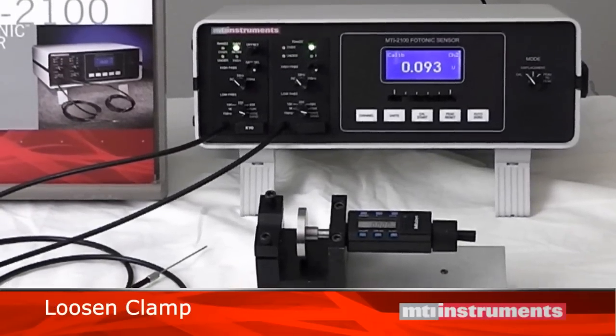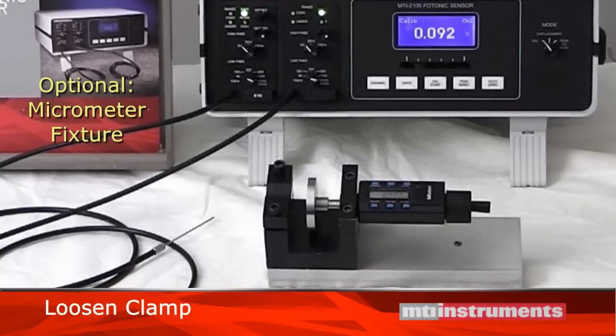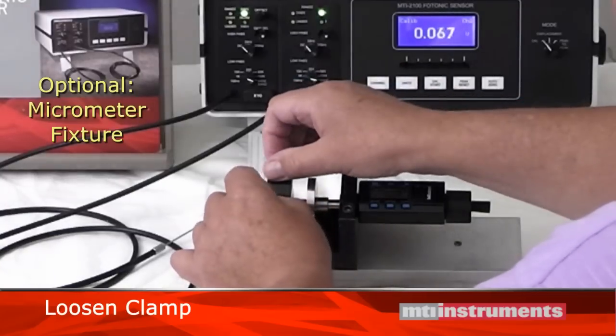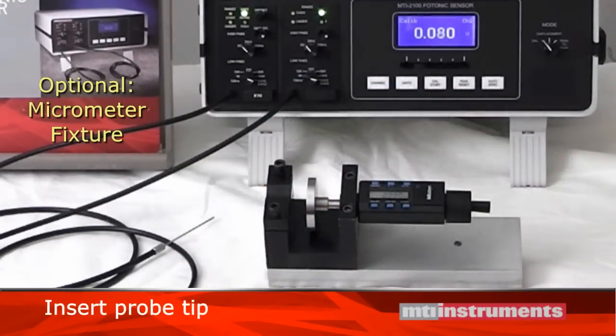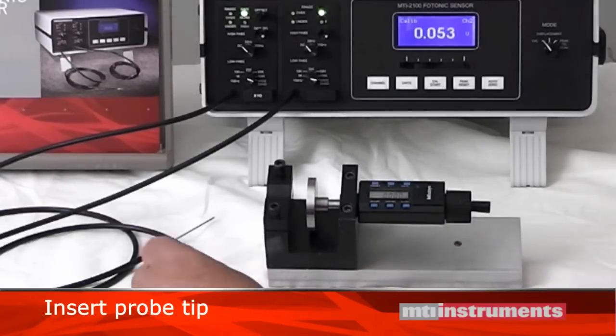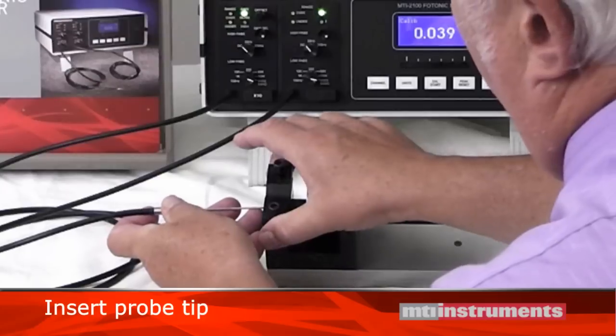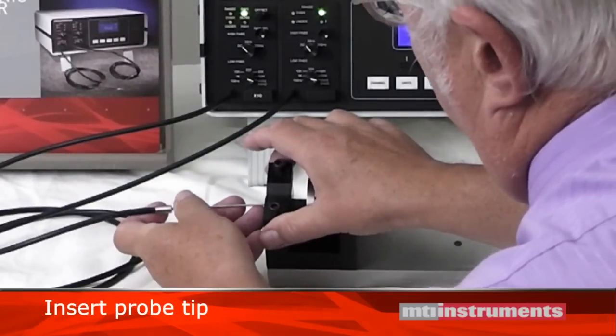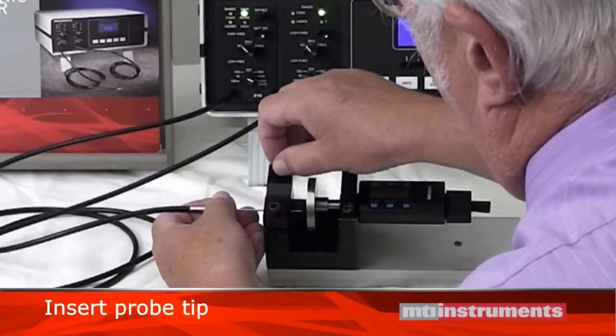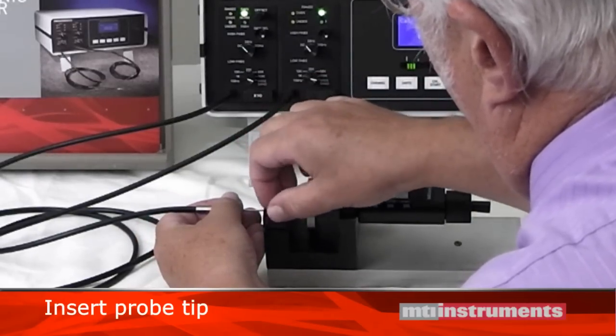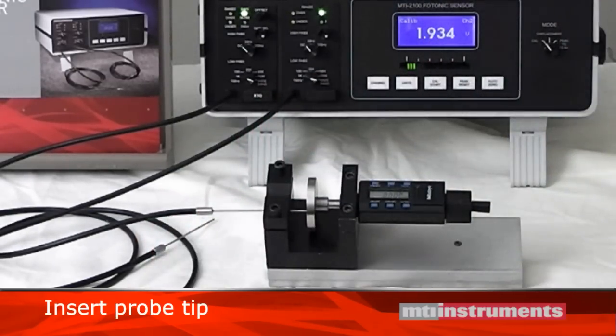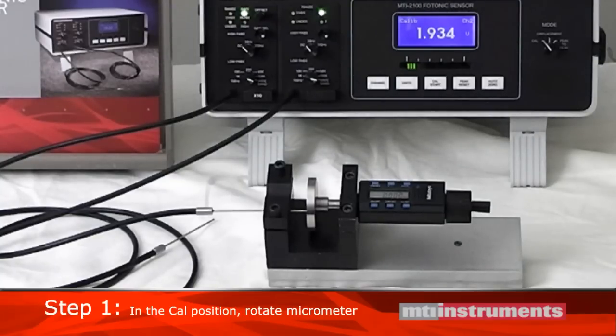While we wait for the lamp and system to stabilize, we can get our MTI Instruments micrometer fixture ready. First, we loosen the clamp. Then, insert the probe tip into the V-groove. When we insert it, we're very careful to make sure that we do not over-tighten it too much, as it could damage the probe tip. We can now start the calibration with 3 easy steps.